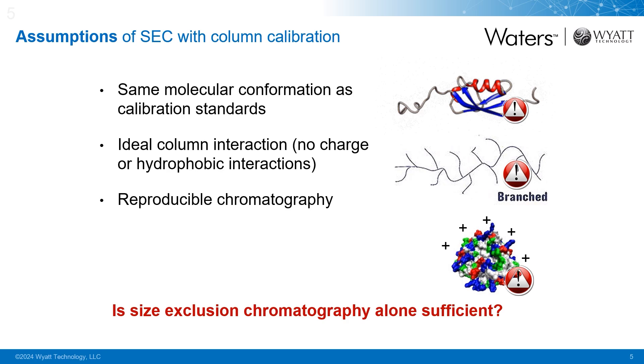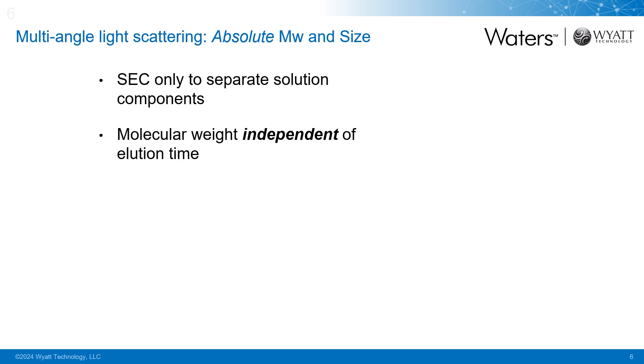As we will see, light scattering can address these weak assumptions by directly and accurately measuring molar mass using first-principle calculations, without the need for column calibration or shape assumptions of any kind. When we add multi-angle light scattering detection to our SEC methods, we no longer need to run column calibration. At that point, SEC is only going to be used to separate our individual species so we can characterize them one at a time as they pass through our light scattering detector. Light scattering will determine your molar mass directly and independently of elution time.